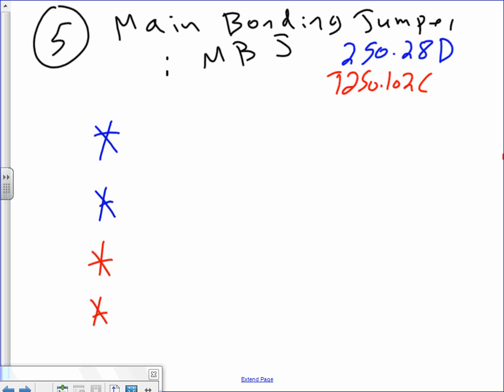250.102C. Size the main bonding jumper from... Everybody knows what a main bonding jumper is? Bonding the neutral to the ground. All right, how do you do it, Chad? Here's how you do it. How many main bonding jumpers do you have in the service? One. No, the main bonding jumper is just a wire. Now, neutral 4. Main bonding jumper is how many? 1. That's just a little jumper.